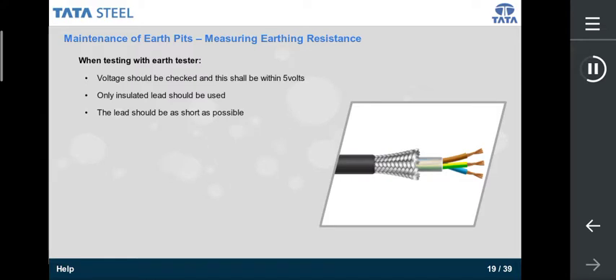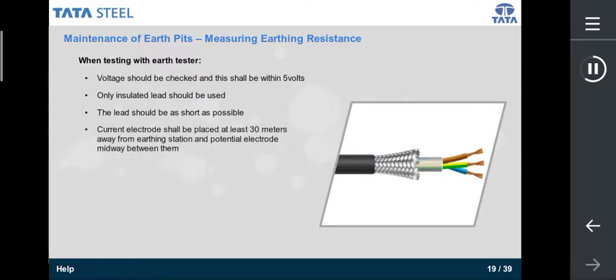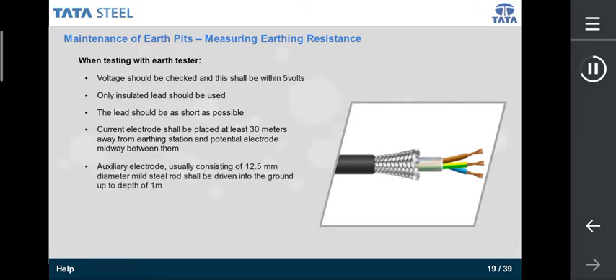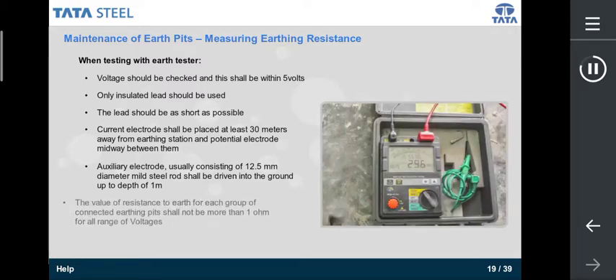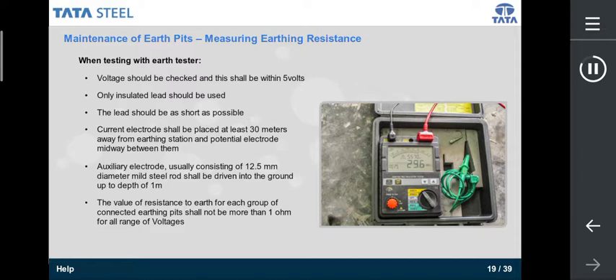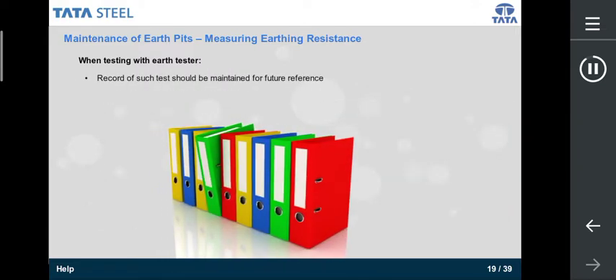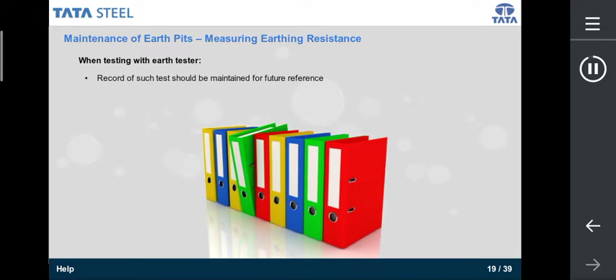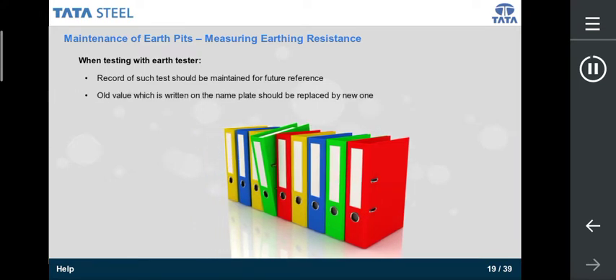Current electrode shall be placed at least 30 meters away from the earthing station and the potential electrode midway between them. Auxiliary electrode, usually consisting of a 12.5 mm diameter mild steel rod, shall be driven into the ground up to a depth of 1 meter. The value of resistance to earth for each group of connected earthing pits shall not be more than 1 ohm for all range of voltages. Record of such tests should be maintained for future reference. Old value, which is written on the nameplate, should be replaced by the new one.